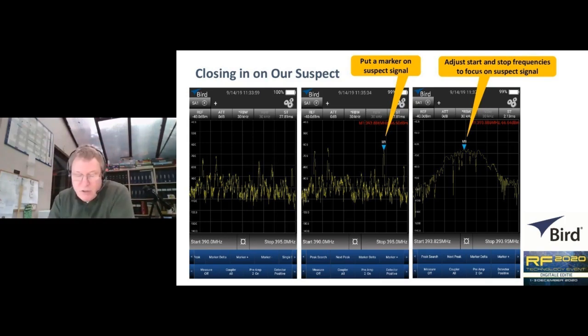We can also close down the resolution and video bandwidths in order that the instrument only sees that one signal. So in this case, we've set it to 30 kilohertz, which is just slightly larger than the channel spacing for Tetra, which is 25 kilohertz.